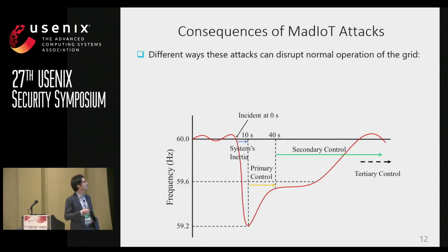In particular, here is the frequency response of the power system to such an attack. As you all know, in North America, the power system operates at 60 Hertz, so before any attack, the frequency should be around 60 Hertz with small fluctuations. At time zero, the attacker increased the demand instantly, which subsequently results in the frequency of the system dropping.